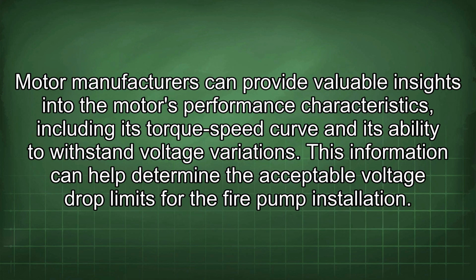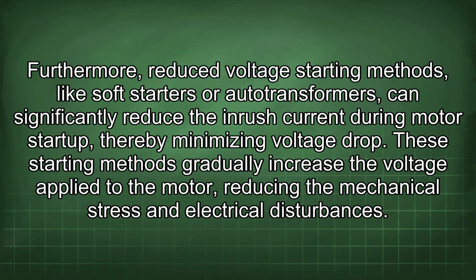Motor manufacturers can provide valuable insights into the motor's performance characteristics, including its torque speed curve and its ability to withstand voltage variations. This information can help determine the acceptable voltage drop limits for the fire pump installation. Furthermore, reduced voltage starting methods like soft starters or auto transformers can significantly reduce the inrush current during motor startup, thereby minimizing voltage drop.